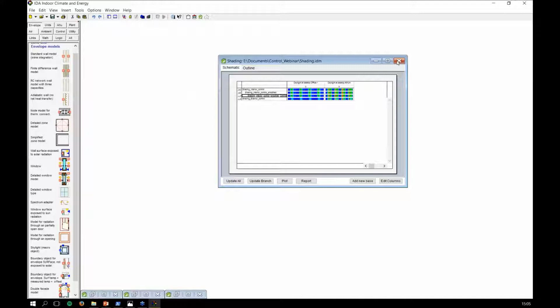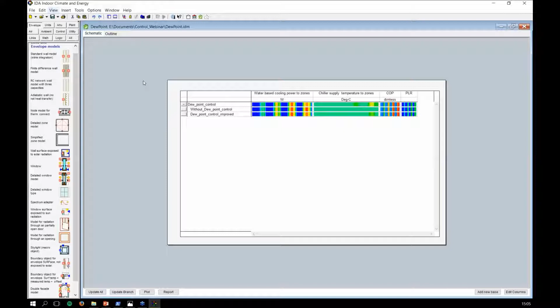Okay, shall we move on to dew point control? So again, I'll maximize this. So what did we want to see in the dew point control? We wanted to visualize the effect the dew point control has on two things. The first is avoiding moisture and condensation. So when you have cooling panels inside and you have high humidity inside, you don't want to supply a low set point for your chiller to these cooling panels, or else you'll have condensation and it'll be a rainforest inside, right? That's not good for us.